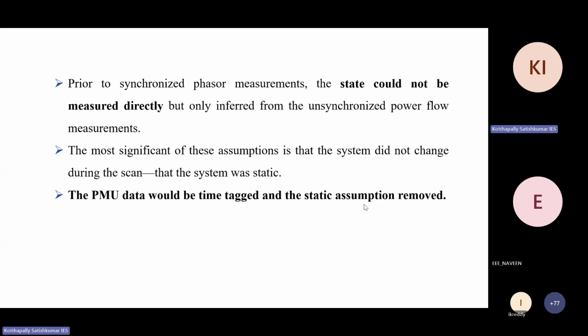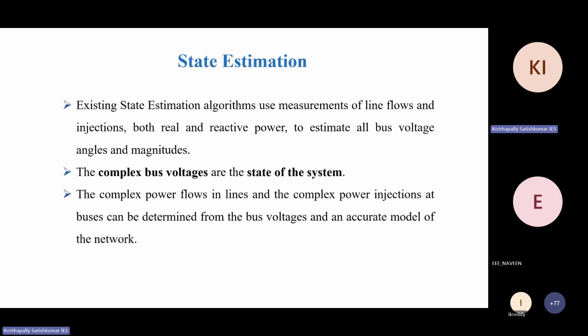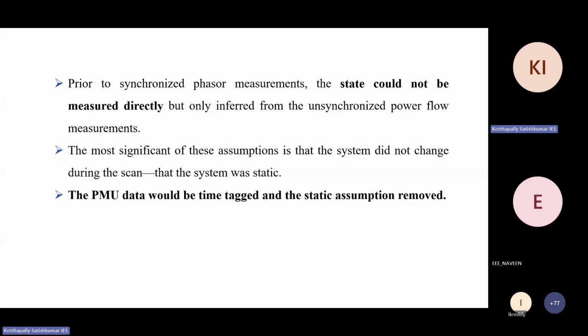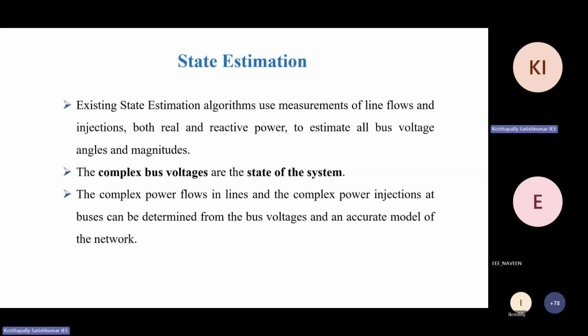It is an assumption because SCADA will not get static data; we get different timing data. But we use this assumption and we run the state estimator till it converges. We use many cycles. It is an iterative process. State estimation is an iterative process because of the static assumption. We run state estimation till convergence. That will converge only when there is data accuracy.